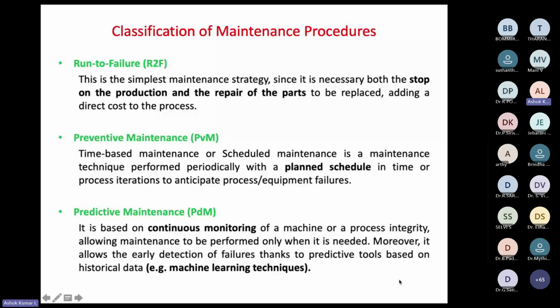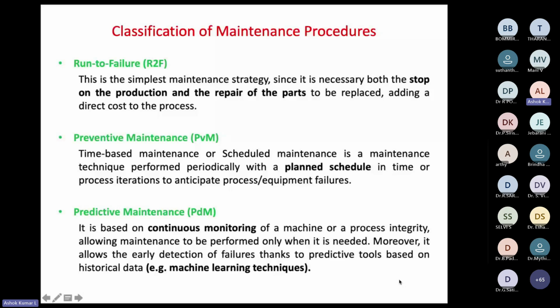Being an electrical engineer, let's say we have a distribution transformer. Regular maintenance activity could include checking the resistance level of the winding, checking earth resistance, checking oil level and oil temperature, whether noise is coming or not, whether the APFC box is working properly, whether the breather is in good condition, and whether the earth pit has charcoal with proper water. These are some checkpoints for planned or scheduled maintenance.